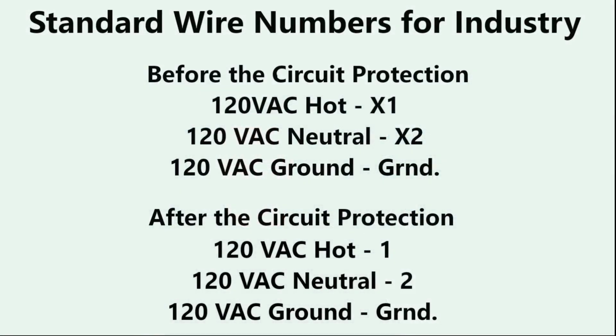All right, now let's take a look at AC. We're going to start with 120 volts. It could be pretty much anything, but 120 is often used as control voltage for a system. So let's take a look at the 120 volt nomenclature. 120 volt hot is usually labeled X1. 120 volt neutral is X2. That is coming from a transformer. And 120 volt ground is always G or GRND or GRD or something that indicates that it is a ground. And it is, of course, normally green.